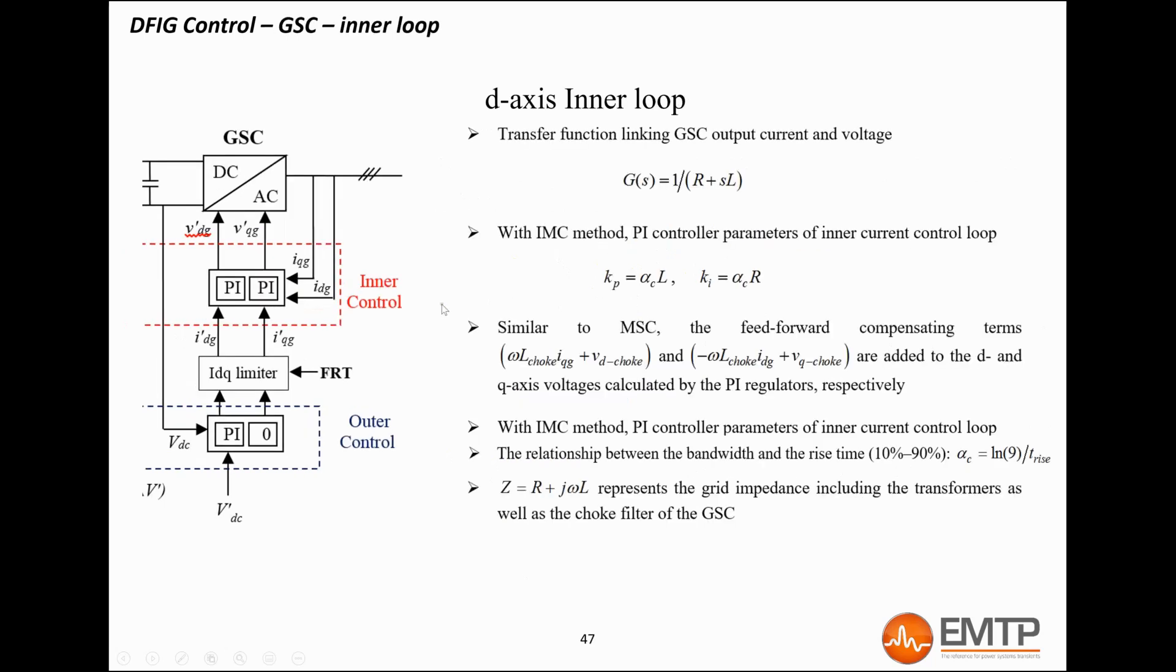For the grid-side converter, the gains of the inner loops depend on the total impedance seen by the converter. The transfer function is shown here, where R and L are the resistances and inductances of the filter choke, the converter transformer, the park transformer, and the grid Thevenin impedance combined. In the generic model mask, users can set the rise time, which determines the inner loop speed. It is typically set to 10 milliseconds. The voltage control is at the converter terminal, but the voltage measured is after the choke filter. Therefore, and similarly as the machine-side converter, the feed-forward compensation is done before putting the converter voltage reference back to the ABC domain.